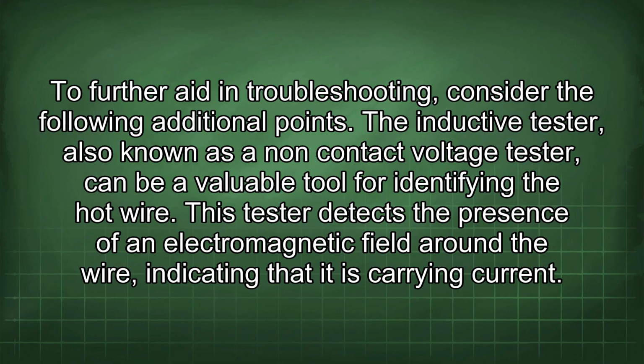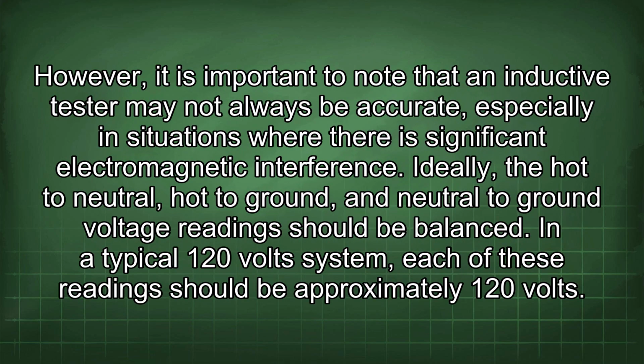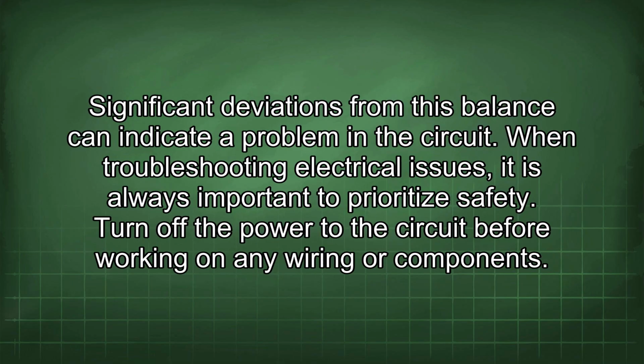The inductive tester, also known as a non-contact voltage tester, can be a valuable tool for identifying the hot wire. This tester detects the presence of an electromagnetic field around the wire, indicating that it is carrying current. However, it is important to note that an inductive tester may not always be accurate, especially in situations where there is significant electromagnetic interference. Ideally, the hot to neutral, hot to ground, and neutral to ground voltage readings should be balanced. In a typical 120 volt system, each of these readings should be approximately 120 volts. Significant deviations from this balance can indicate a problem in the circuit.